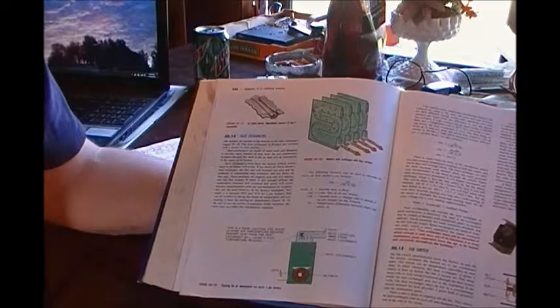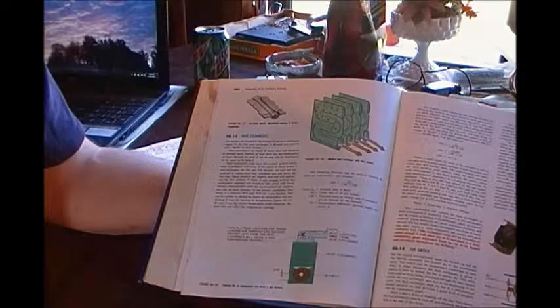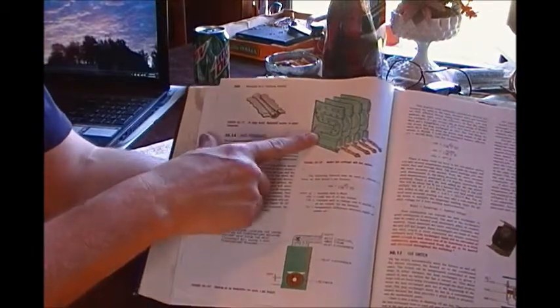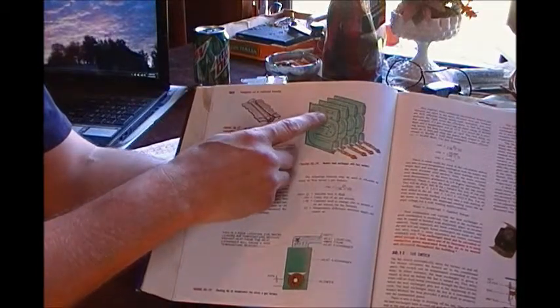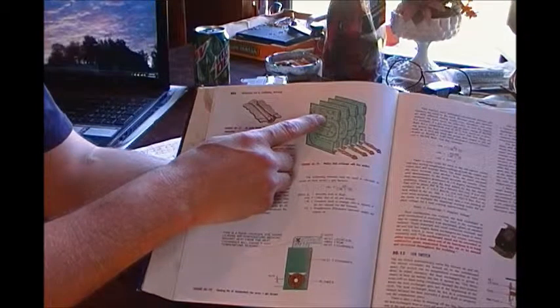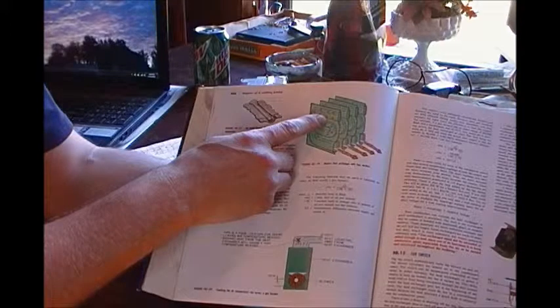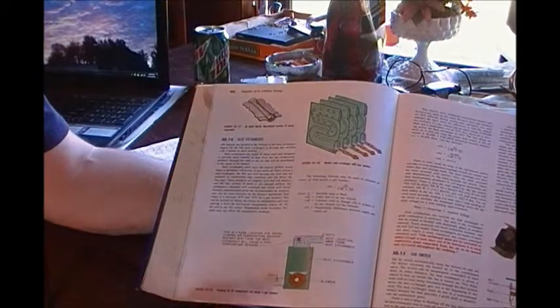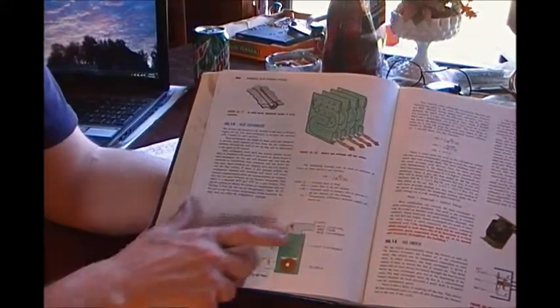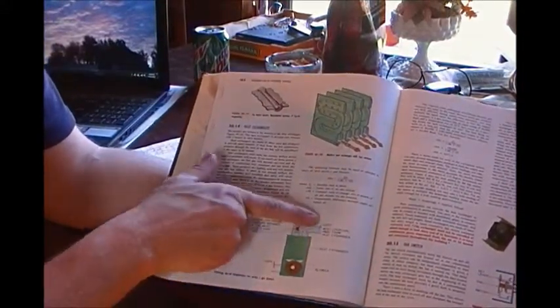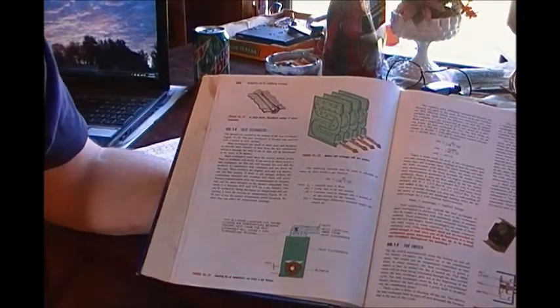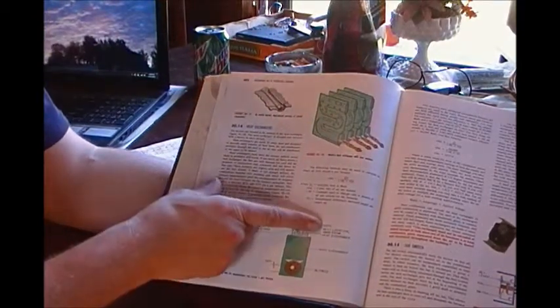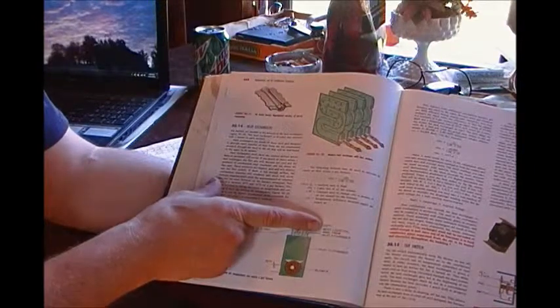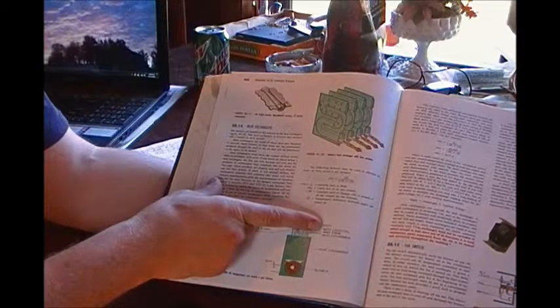Now, if we were running at 170, we're way over our 40 or 70 degree difference, and what that'll do is it'll burn a hole in your exchanger, it'll crack, whatever, and you'll start getting flue pipe, you'll start getting carbon monoxide into your supply, and it's going to cause an issue. Now we've determined where we got to be within 40 to 70 degrees difference, air going in, air coming out, and we have a gas pressure of 3.5, but yet we still are exceeding the recommended 40 to 70 degree difference. We're pumping out 170.